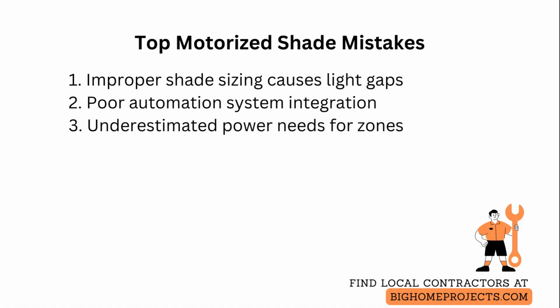A third concern is underestimating power needs for grouped zones, creating weak or slow movement, and the remedy is to calculate total motor wattage per circuit and either add dedicated circuits or distribute loads across multiple controllers.